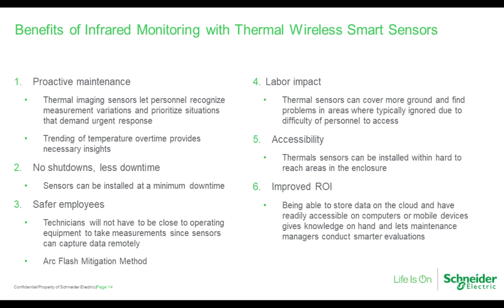Accessibility. Thermal sensors, again, as I discussed earlier, can be installed within hard-to-reach areas and enclosures. And using a wireless sensor, this information can be sent back, and the sensors never have to be interacted with again after they've been installed. And most of these sensors are battery-less, so they do not need a battery replacement sometime in the future. So you don't have to get back into the equipment once these are installed.